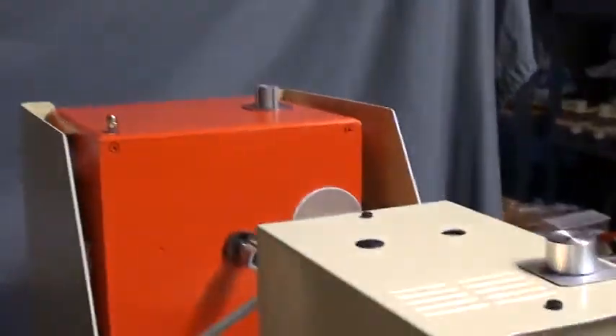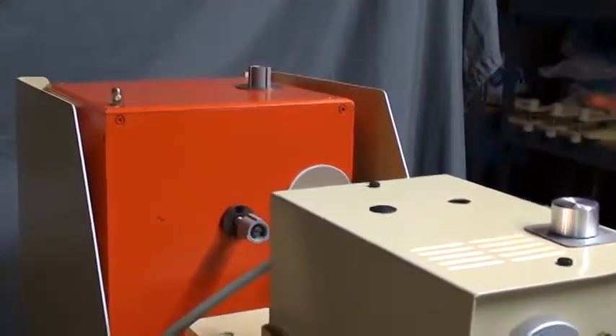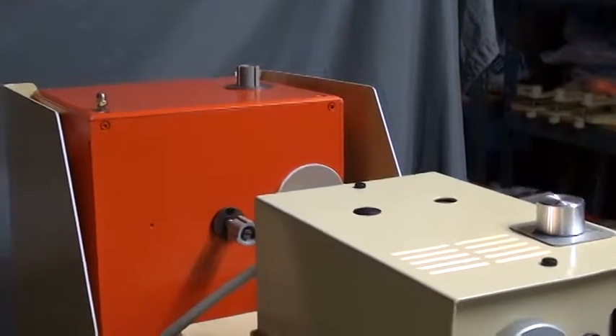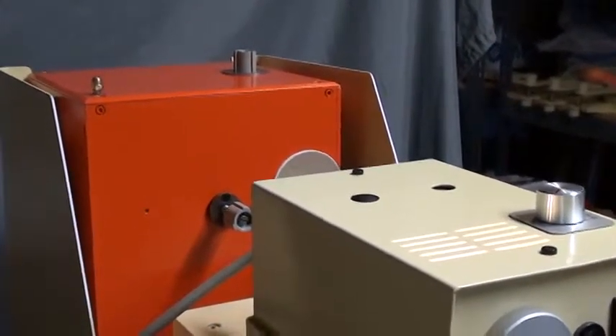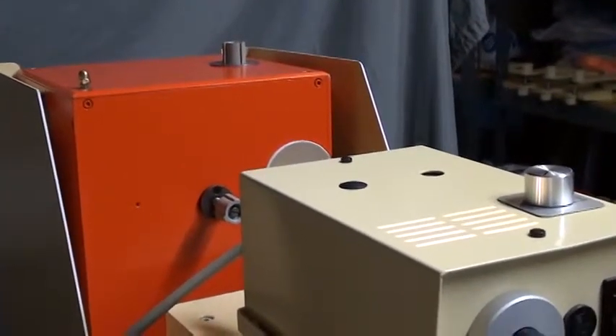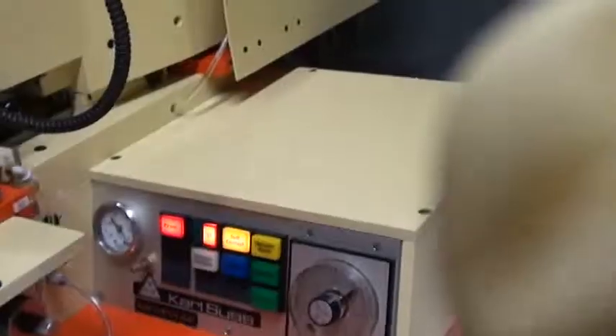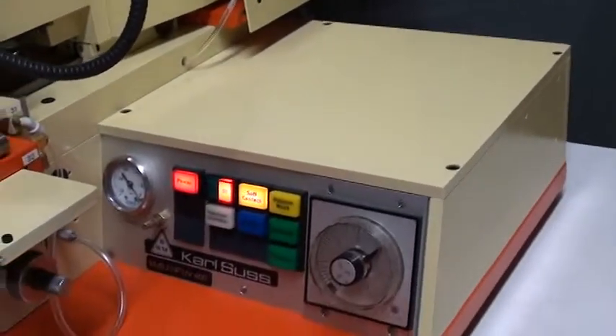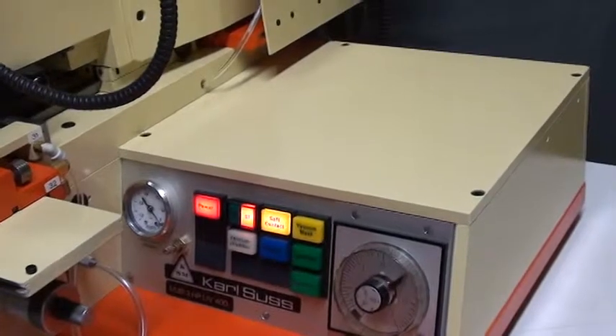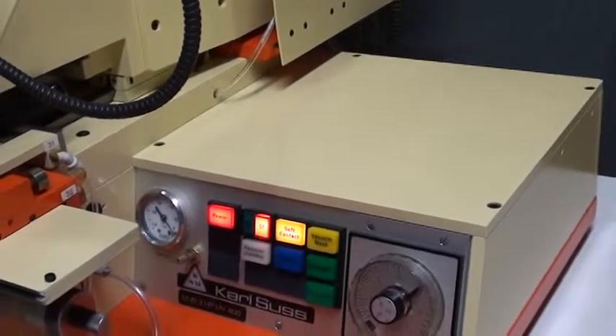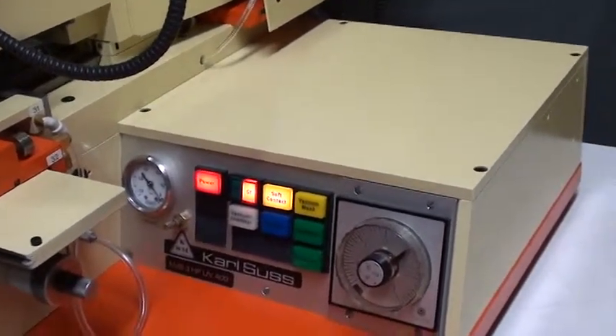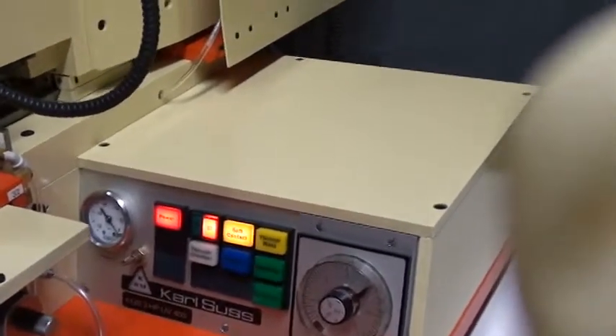The lamp house assembly has been completely disassembled and installed with new cables, and all axes have been lubricated with a high temperature lubricant. Internal to the machine, all valves have new O-rings, new air fittings, and new tubing. All new panel lamps have been installed.